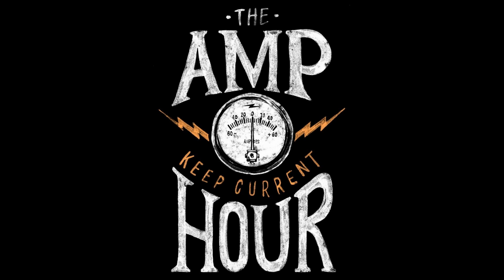Huh. It is an interesting way to think about it too, like my own migration of how I've thought about batteries over my career. It was always voltage at first, and then current, but really thinking about internal resistance, really impedance I suppose, of the battery is the best way to think about it, especially during delivery of power back out. And there is a simpler and a much more complicated model of that impedance. It's a complex impedance when you start to really drill down into it.